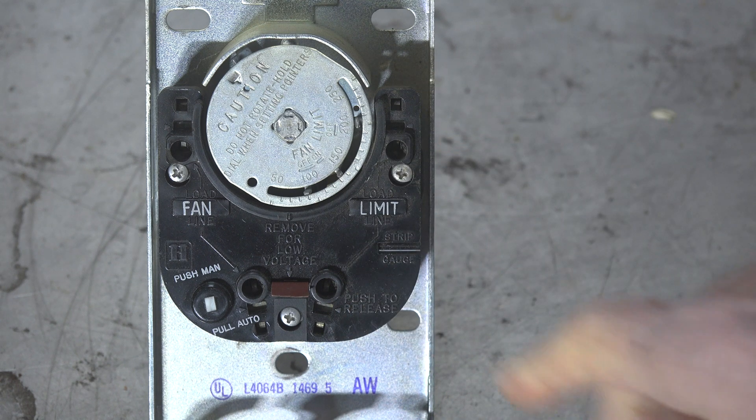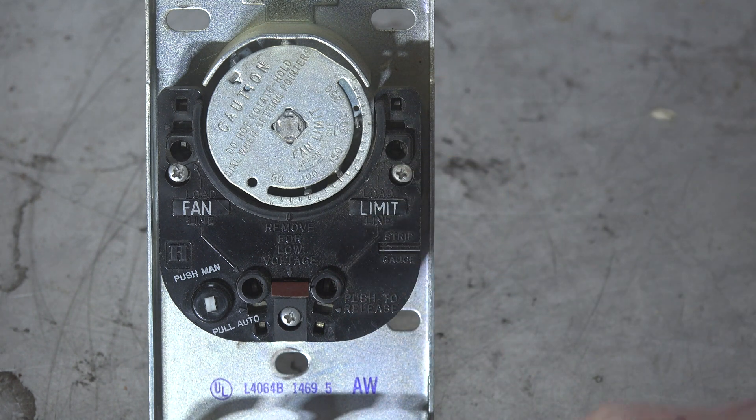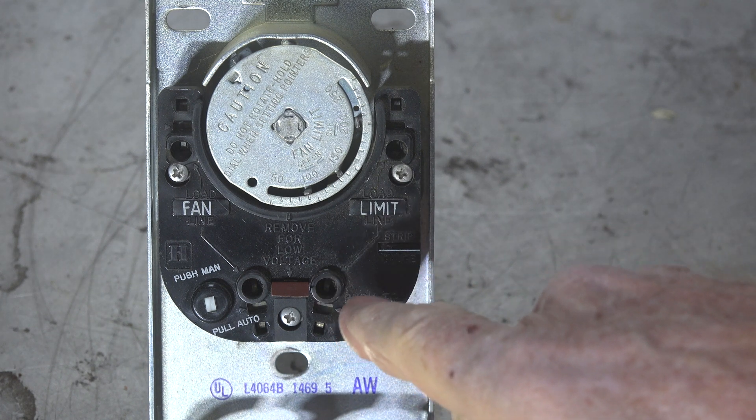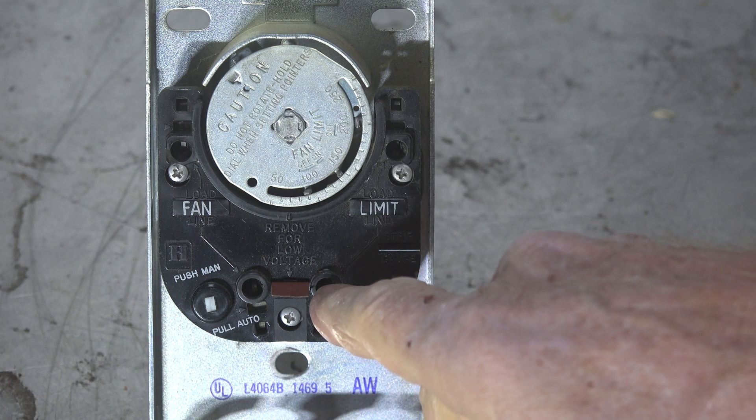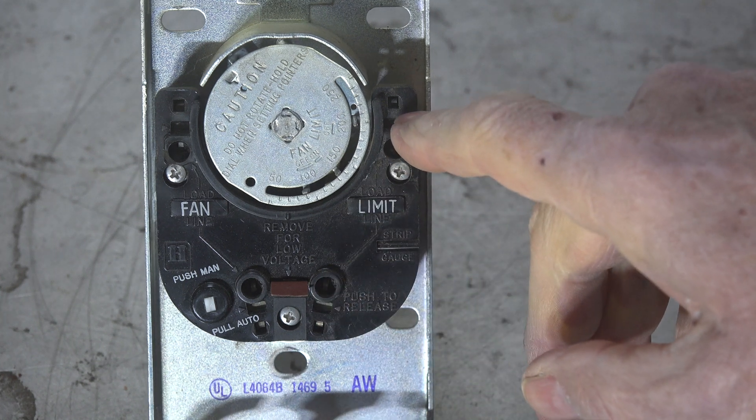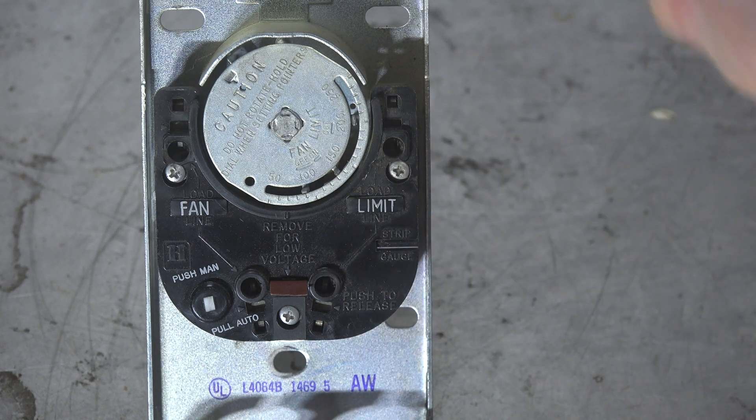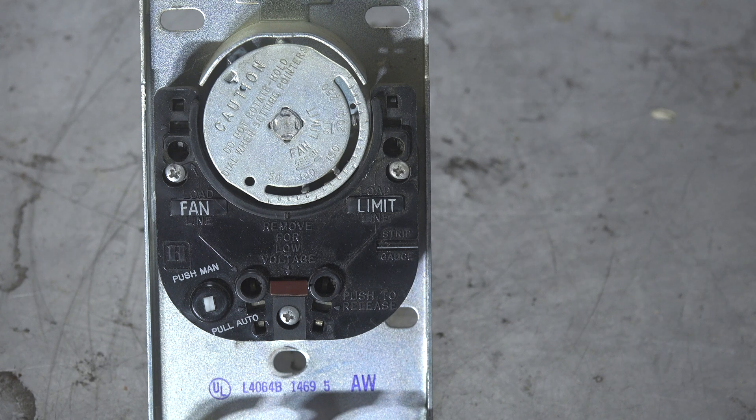Then you take your 24-volt circuit that goes to the gas valve and you interrupt it there. So I would have the power coming from, say, the thermostat would come to here, and then the gas valve would be hooked up here. So that would be in the line; it would shut it down if there was an overheat.